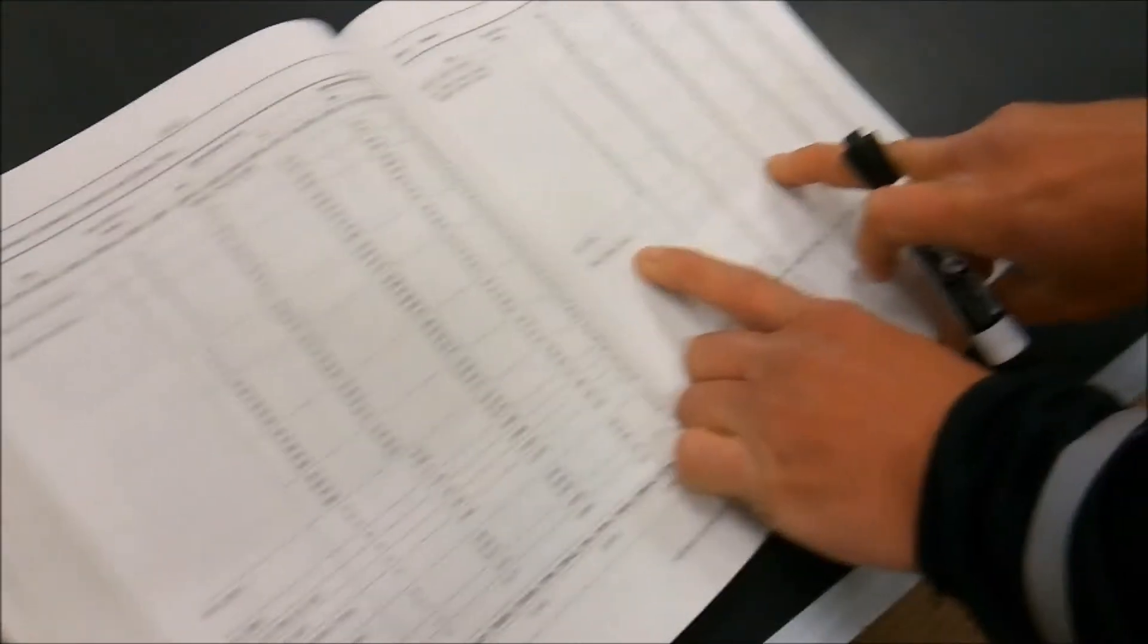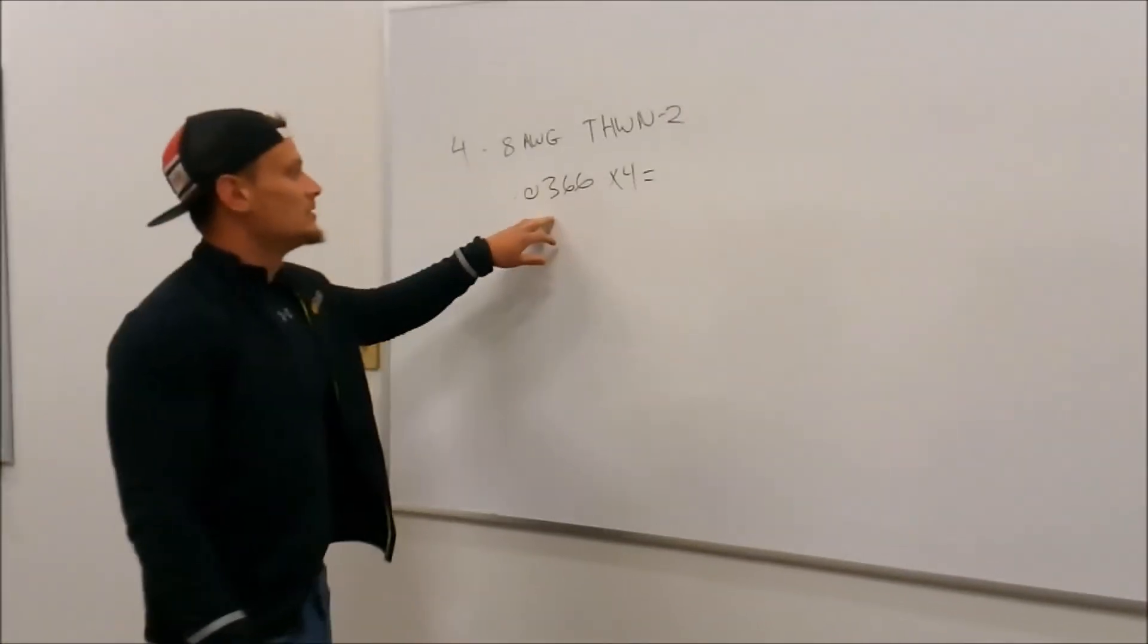So go to the 8 gauge area, we find it's 0.0366. 0.0366. And then multiply it by 4. So 4, 8 gauge THWN2 wires gives us, each one is an area of 0.0366 square inches. Multiply that by 4 gives us 0.1464. So we need to find conduit that will have at least that area.